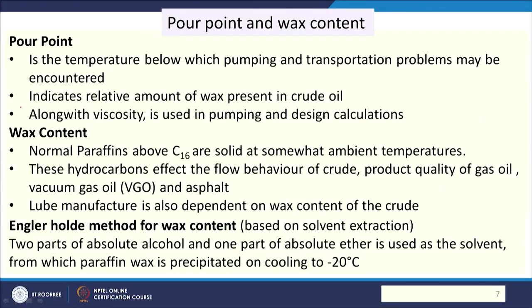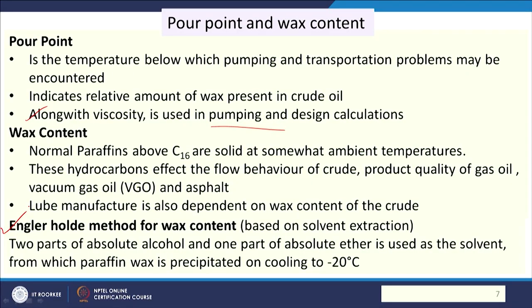Another property is pour point and wax content. Pour point indicates flowability — it is the temperature at which the fuel ceases its flow. It is related to wax content: more wax means the flow is more easily seized. Together with viscosity, pour point is used for pumping design. Paraffins with carbon number greater than 16 are solid, and these solidified paraffins are considered the wax. Wax content is determined by the Engler-Holde method using solvent extraction — absolute ether and absolute alcohol — and paraffin wax is precipitated at minus 20°C.